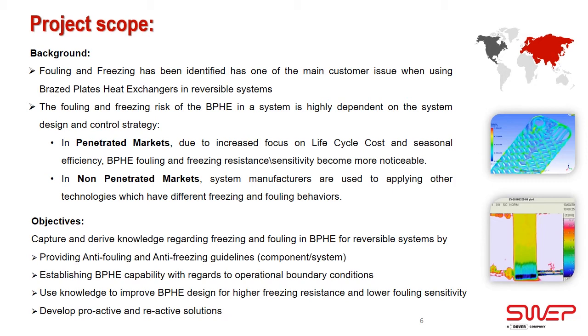The second kind of market is the non-penetrated market, like North American heat pump, for example. System manufacturers are used to other heat exchanger technology as a standard, and as already explained by Adam, a fear or concern exists about freezing and fouling in regards to BPHE technology. So, in order to support the integration of the SWEP brazed plate heat exchanger into our customers' systems, for all kinds of markets, we decided to initiate a freezing and fouling project.